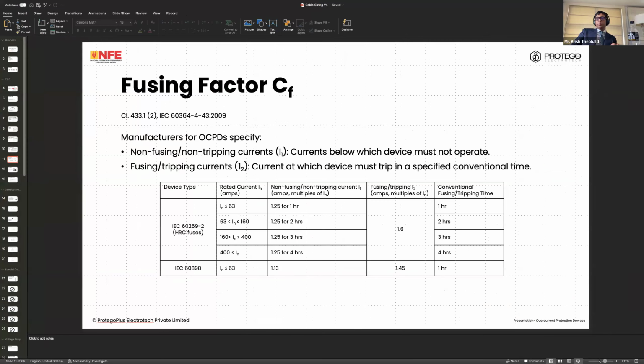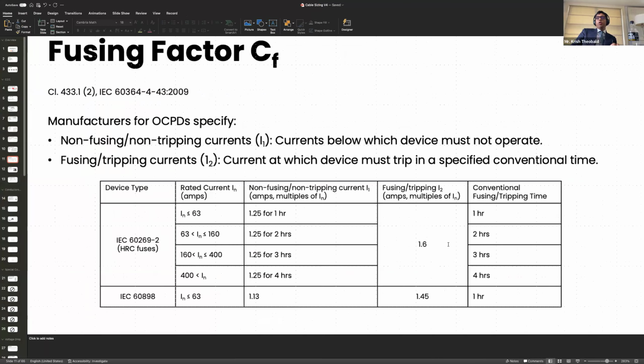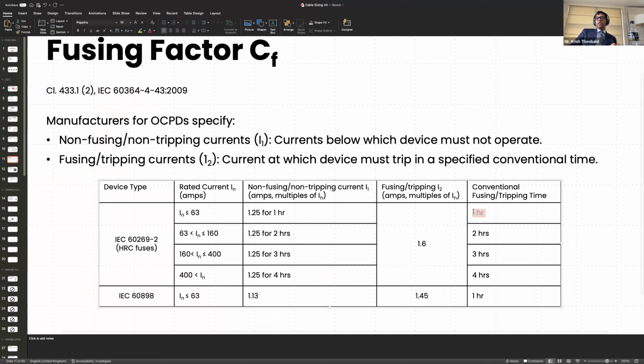This is an excerpt from the product standard. I2 is calculated on the basis of conventional time mentioned in the product standard. The reason this value increases as the rating increases is that when you use a higher size cable, they can withstand overload for slightly longer. So you don't have to calculate I2. I2 is given to you by the manufacturer for a given time. You don't need to do any calculation yourself.